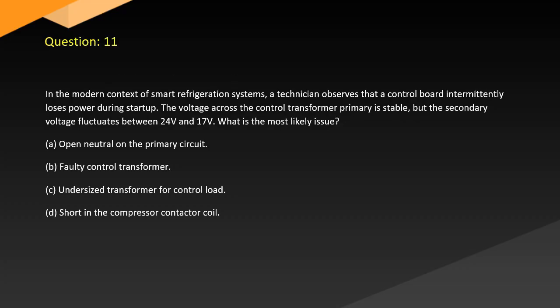Question 11. In a modern context of smart refrigeration systems, a technician observes that a control board intermittently loses power during startup. The voltage across the control transformer primary is stable, but the secondary voltage fluctuates between 24 and 17 volts. What is the most likely issue? A. Open neutral on the primary circuit. B. Faulty control transformer. C. Undersized transformer for control load. D. Short in the compressor contactor coil.